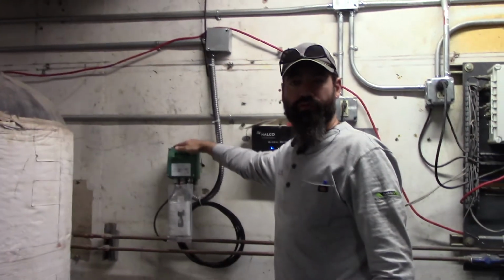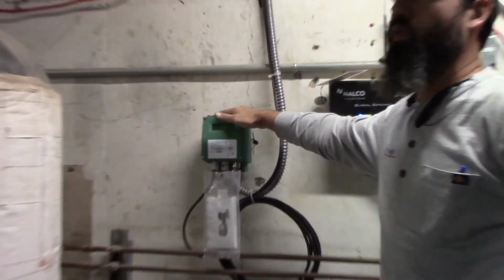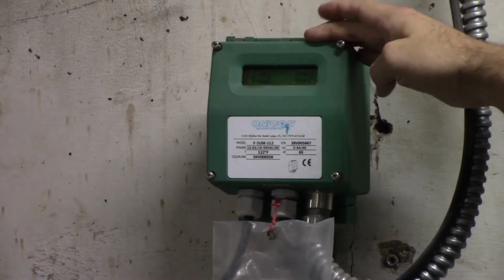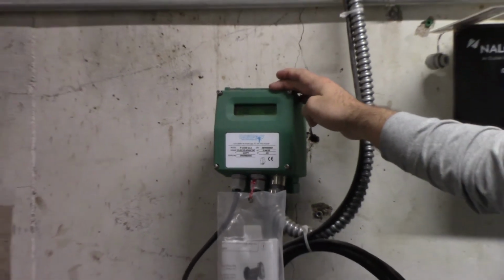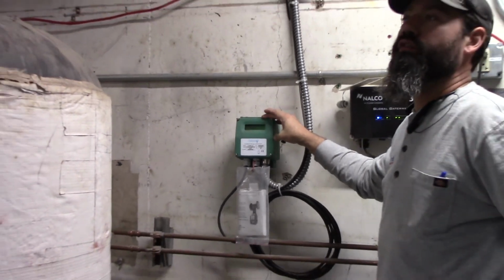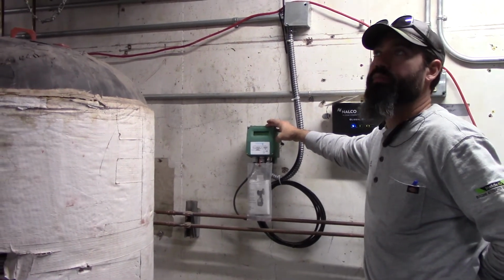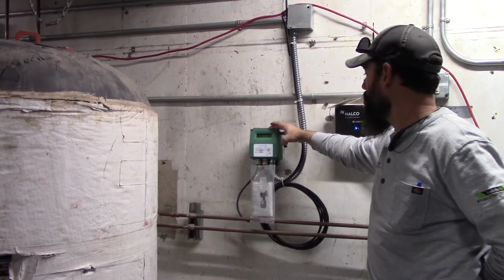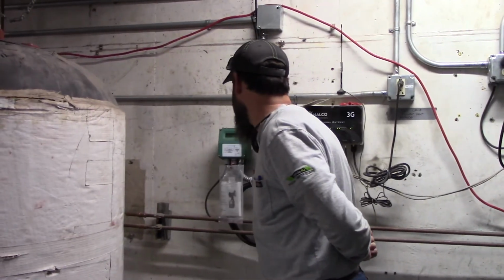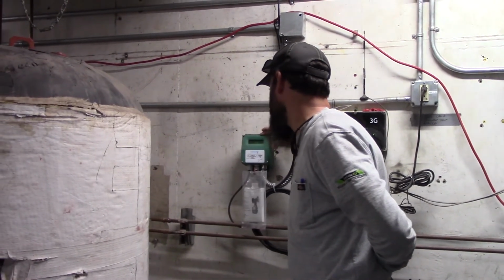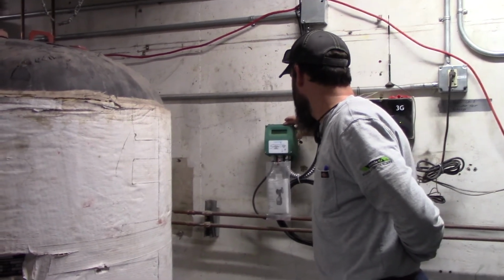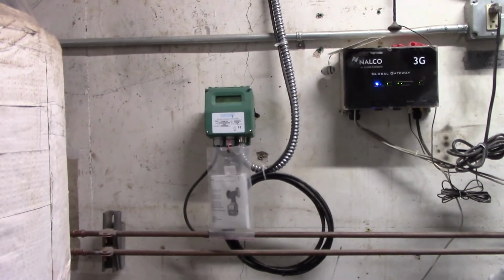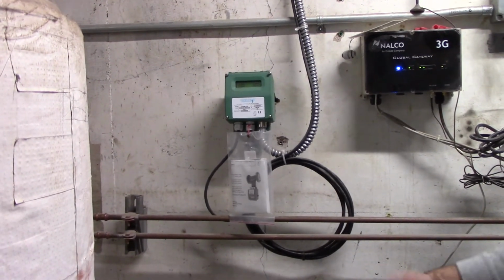We've got a few flow meters in this room. This is on the north wall, just north of the heat pump chiller. So you can see what kind of chilled water you're pulling to the 56-degree loop from the chill water supply at the district loop. And right now it's going to be fairly low, I would imagine. Just have to wait for it to cycle through. We're not showing anything, which is what I would expect to see, because we're pulling the majority of the chilled water for the 56-degree loop from the return side.